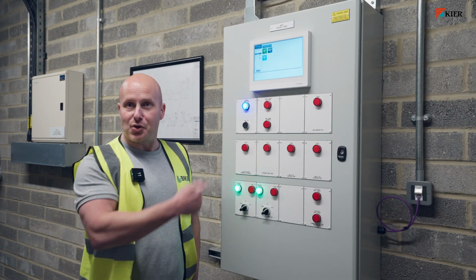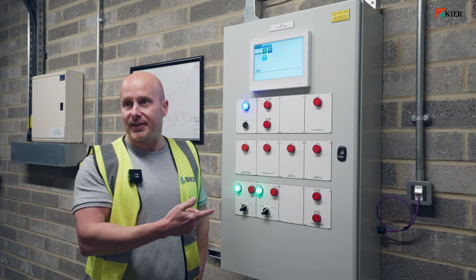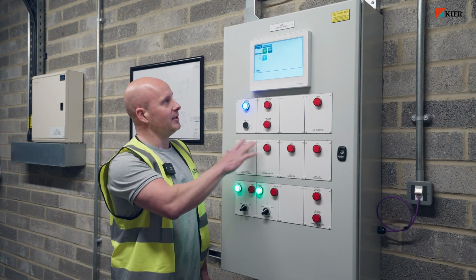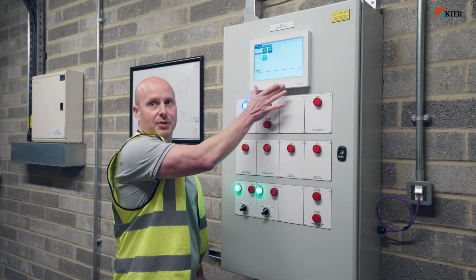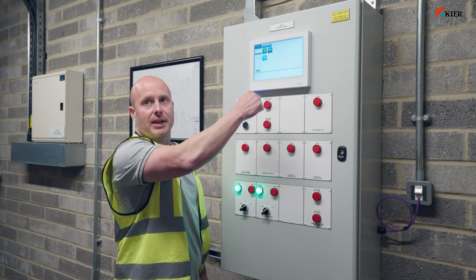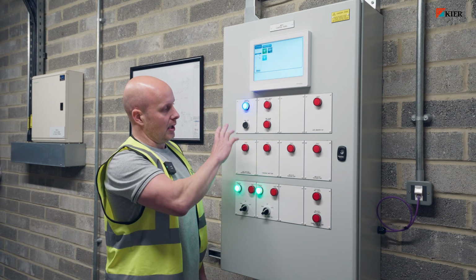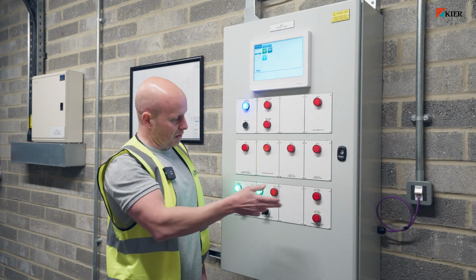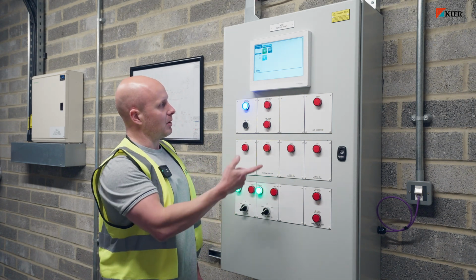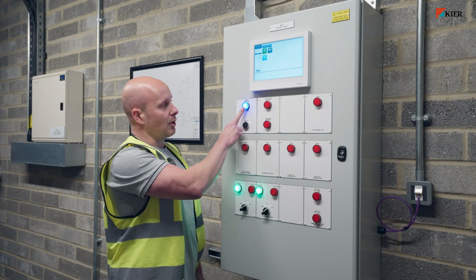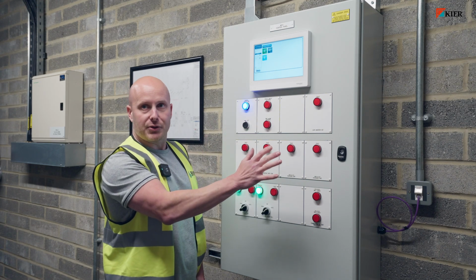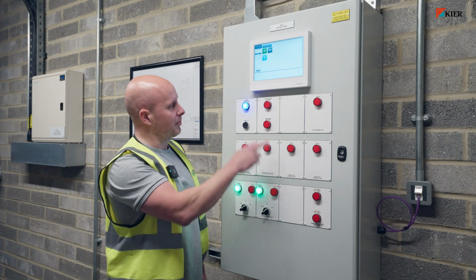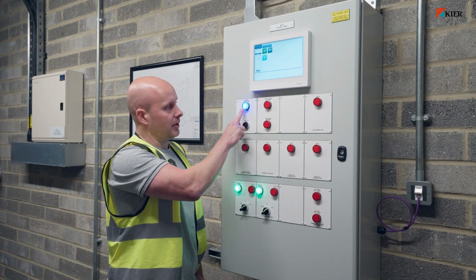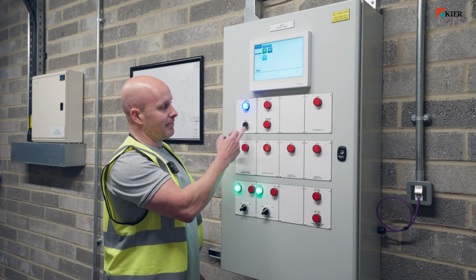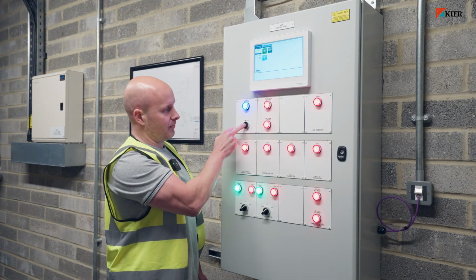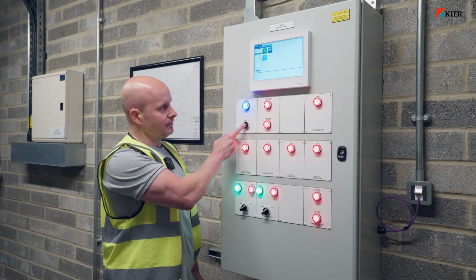Okay, this is the BMS control panel for this site. It's quite a basic setup. As you can see on here, you have your what's called a HMI, human machine interface. We'll run through this later just to go through the graphics. On here displays all your faults and all your points that are enabled. We have control circuit live lamp. So obviously if we have no power, nothing will be on here at all. If a circuit breaker or a fuse pops, this will go off, so that'll give you an indication. This should always be on. We have this lamp test button just to very quickly test all the lamps. As you can see, all the lamps are working.